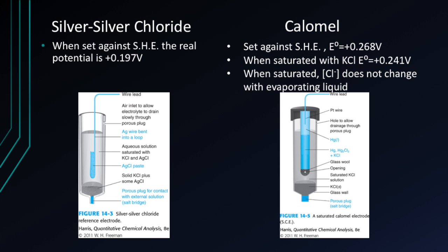Here is a reiteration of the structures of the silver-silver chloride and the calomel electrodes. The silver-silver chloride electrode is 0.197 volts vs. SHE, and the saturated calomel electrode is 0.241 volts vs. SHE. When it is not saturated, it's actually 0.268 volts. When saturated, the Cl⁻ concentration does not change with evaporating liquid.